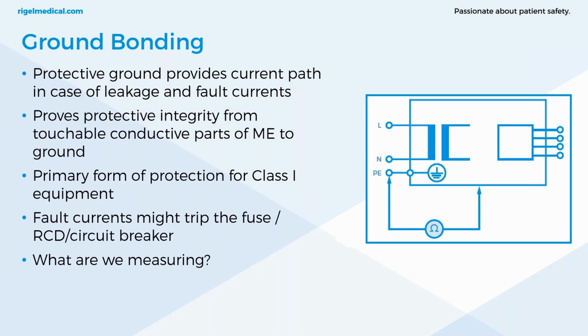Protective ground provides a current path in case of leakage and fault currents. There are several types of class 1 medical electrical equipment that have exposed conductive connectors. Patient beds are a good example. So we need to ensure that the current path is available if there are fault currents on those exposed connections.